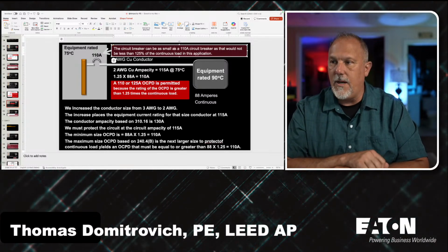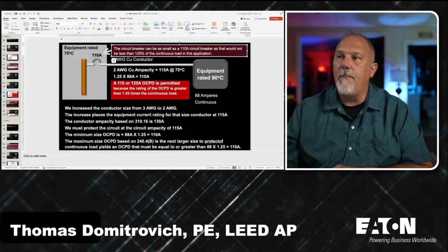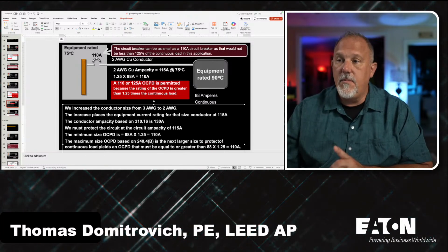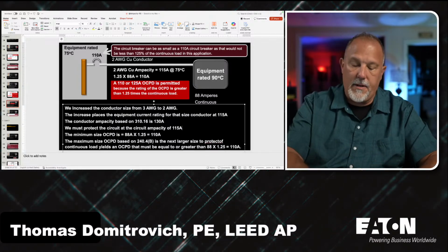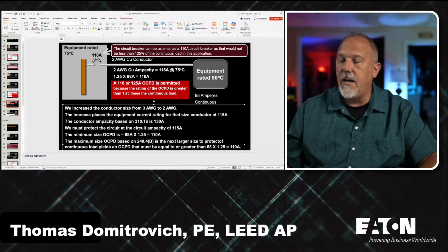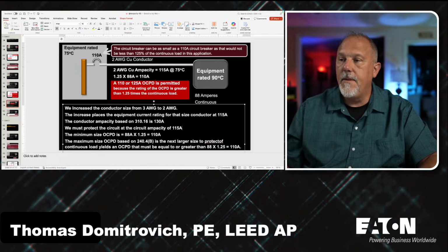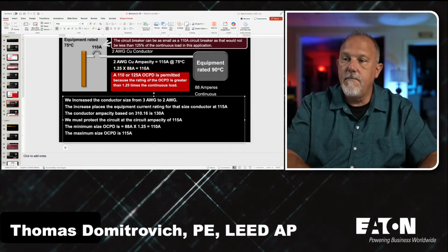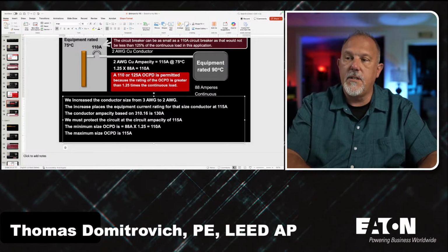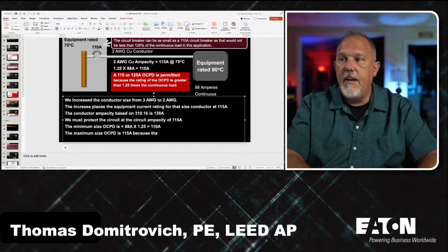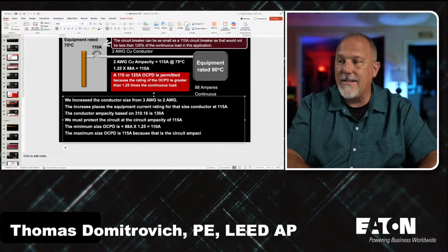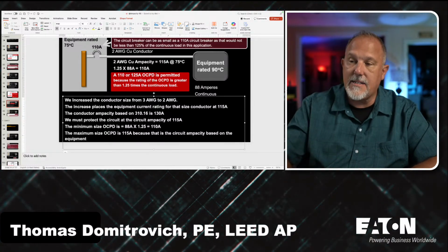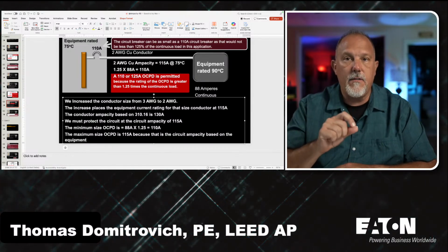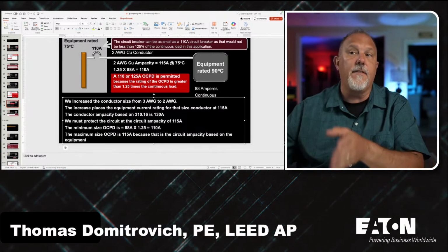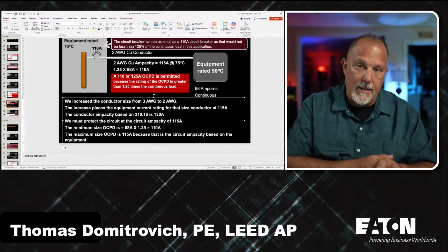The circuit ampacity is what? 115 amps. The breaker cannot be greater than 115. We must protect the circuit at the circuit ampacity of 115 amps, period. The minimum OCPD size is 110 amps. The maximum size OCPD is 115 amps because that is the circuit ampacity based on the equipment. I can't exceed 115 amps with that size conductor for the equipment. It has nothing to do with the ampacity of the conductor itself. It's the equipment that is the limiting factor.